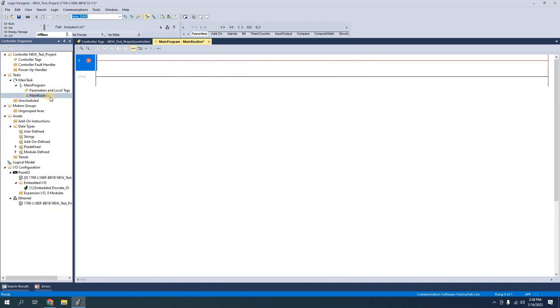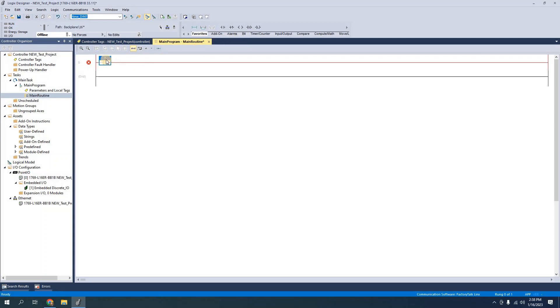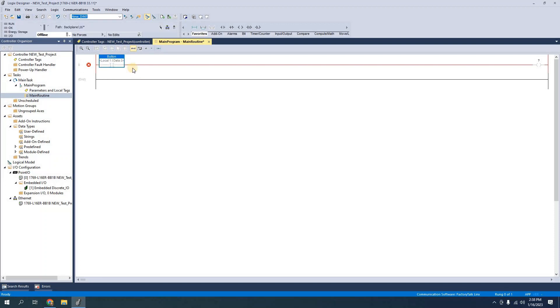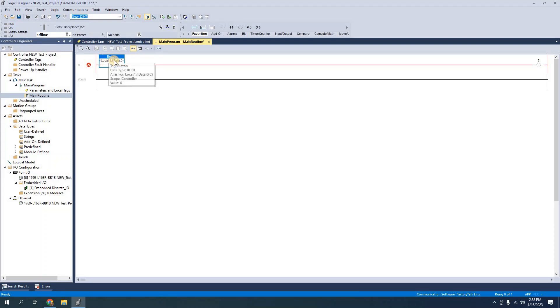When I'm in my main routine I can pull in an examine on which is an XIC examine if closed command and I can do the same with an output energize. I'm going to select button which if I just start typing button you'll see it start auto filling here and when I hit enter I see the tag that I've created and I see the base address for it. That's really useful for troubleshooting because I know where button is physically connected on the controller.